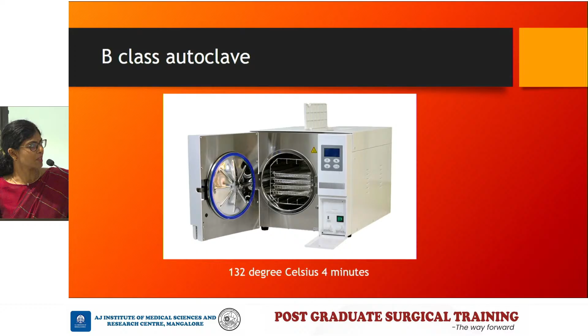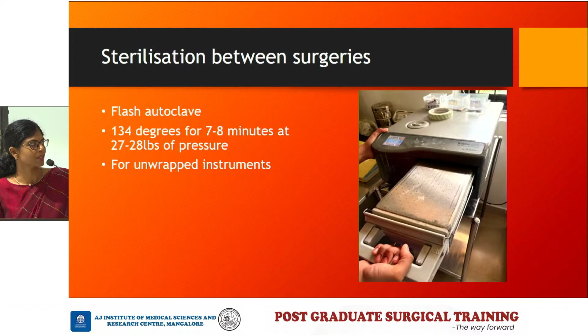When you have to do sterilization between the surgeries, that is, you have an instrument which you need to reuse and you don't have enough sets, then you go for what is called a flash autoclave. Now, flash autoclave has a cassette basically like this, so all the instruments don't have to be wrapped, only cleaned and dried and put in this, and then in 7 to 8 minutes your sterilization will be done.